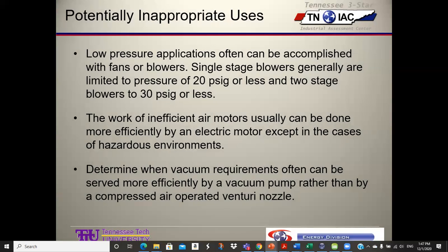They generated air at 100 pounds of pressure, and then they proceeded to drop it to 10 to 12 pounds in order to spray in the media center. What a waste. Pump it to 100, drop it to 10 or 12. You can get a blower that would easily go up to 10, 15, 20 horsepower. I mean pounds per square inch, and use probably 20 to 30% of the horsepower, save a bunch of energy.